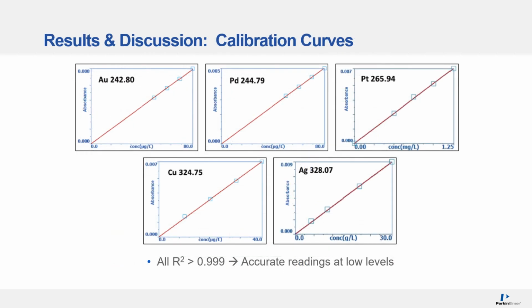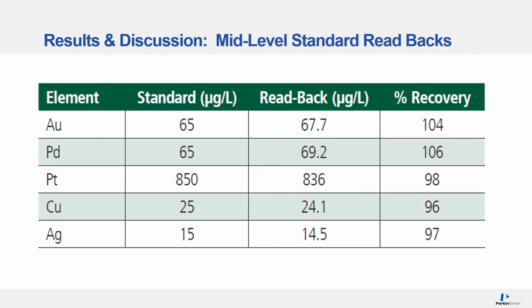And here are the calibration curves. So we had linear curves for all of these, and the R squared for all curves was greater than 3 nines, showing the accuracy of the system. And as well, we created some mid-level standards since every calibration curve contained 4 standards. We chose the mid-level of each one of those curves, created a new standard, and tested the readback on those. So you can see the results in this table here, where our recoveries were all within very tight margins.